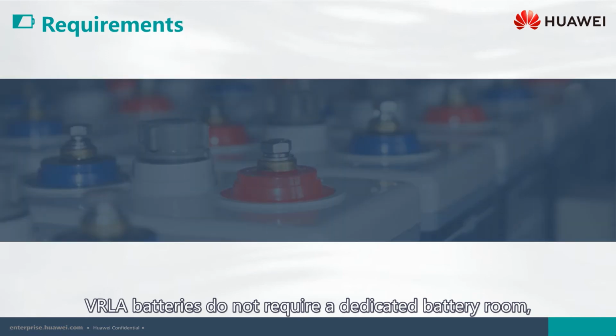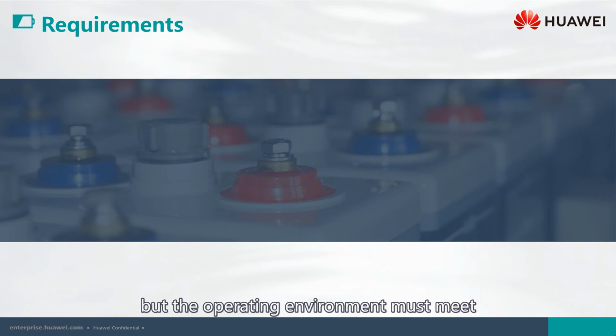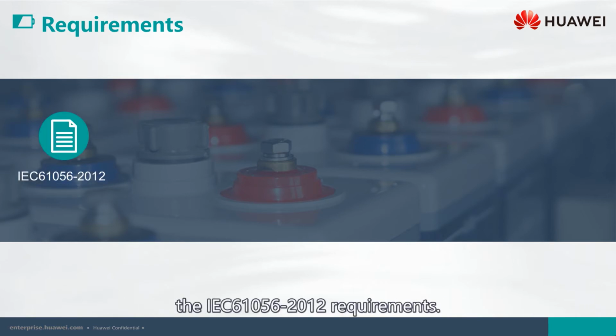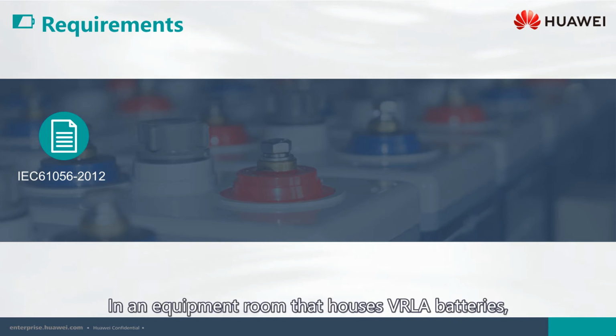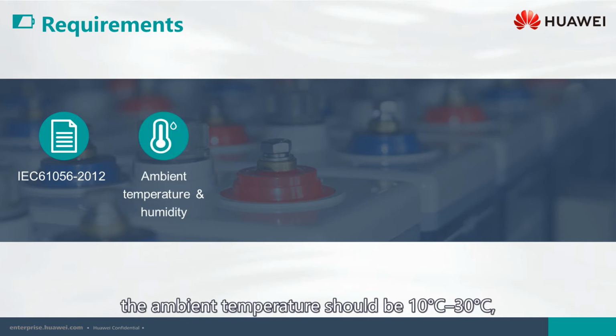VRLA batteries do not require a dedicated battery room, but the operating environment must meet the IEC 61056-2012 requirements. In an equipment room that houses VRLA batteries, the ambient temperature should be from 10 to 30 degrees Celsius, and the relative humidity should be from 20% to 80%.